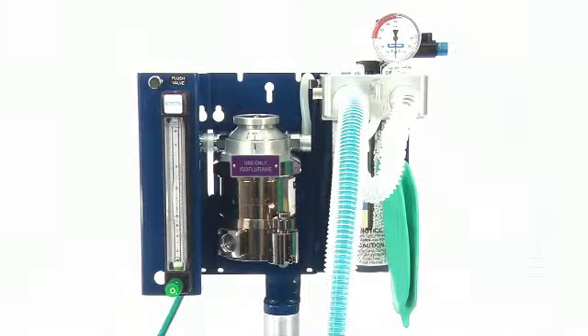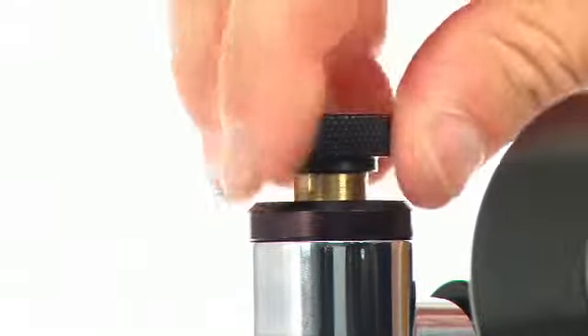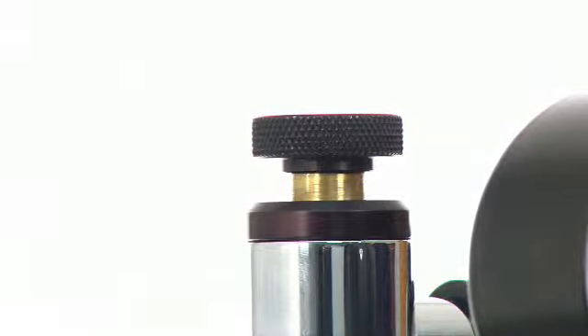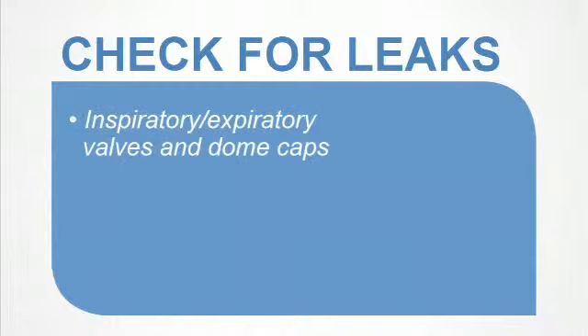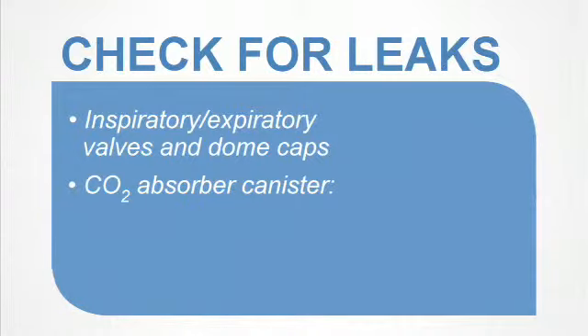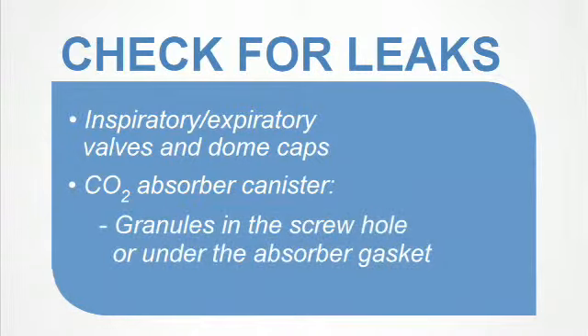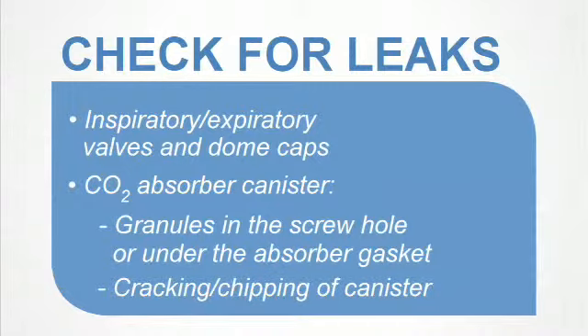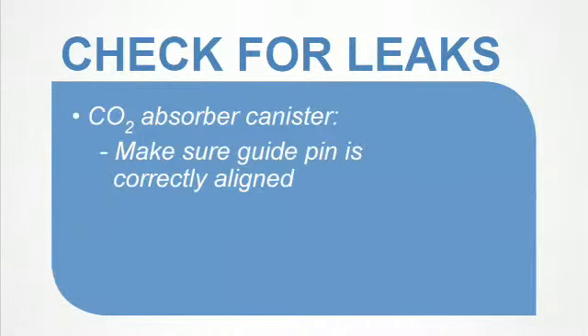After your CDS 9000 machine has passed the leak test, make certain you relieve the pressure by opening the pop-off valve. Common places to check for leaks: inspiratory and expiratory valves and dome caps, CO2 absorber canister. Check for granules in the screw hole of the divider or under the CO2 absorber gasket on the underside of the machine head, or cracking, chipping of the canister. Ensure the guide pin is correctly aligned with the guide pin hole on the underside of the machine head.